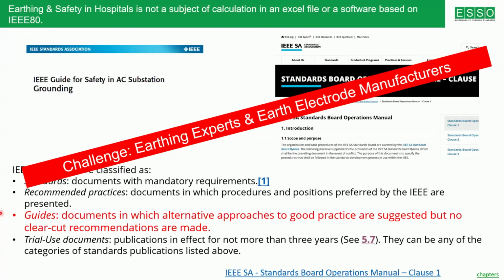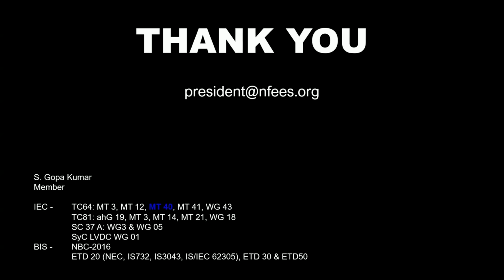62305 explains the earthing requirement for lightning during the time of lightning, whereas the earthing requirement for a hospital, it depends, or the subject is explained in more than 50 standards. The standards which are related to the biomedical equipment, the standards related to the supply system, the standards related to the high voltage installation, the standards related to switchgear, control gear assembly, or UPS, and so on. So it is not an easy subject. Please note, I was mainly focusing on protective earthing. There is also a big subject of functional earthing.